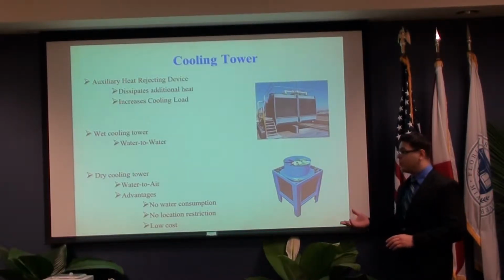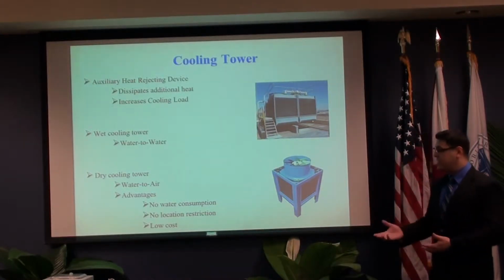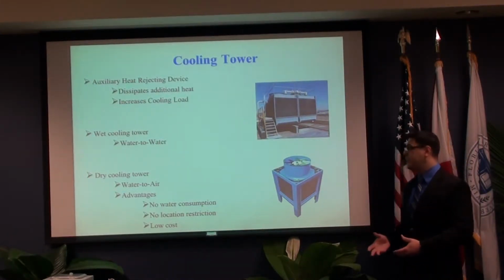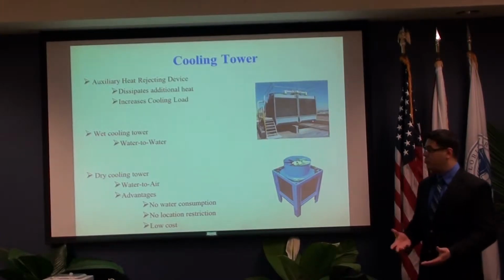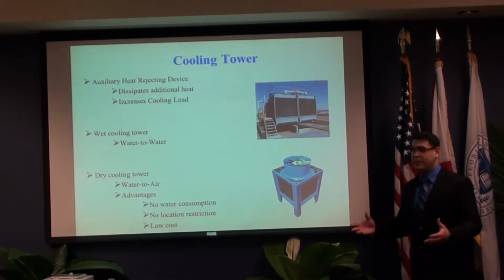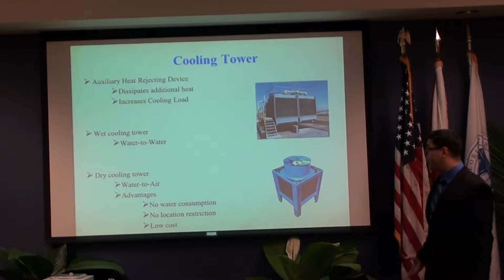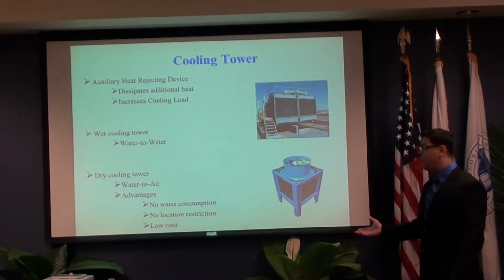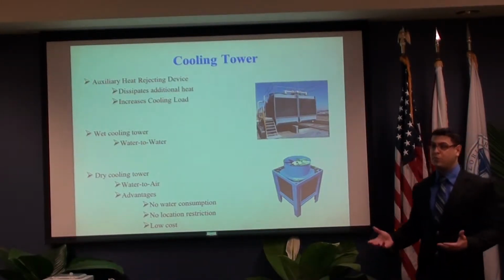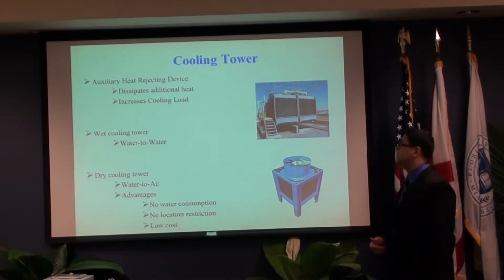The advantages of the dry cooling tower, which is the system that we did, are that there is no water consumption, which means it's more environmentally friendly. There's also no location restriction, meaning you don't have to place the dry cooling tower anywhere near a water source. And finally, it's low cost because you don't have to worry about bringing water to a site, which is very, very expensive.